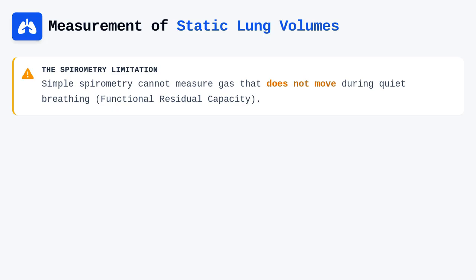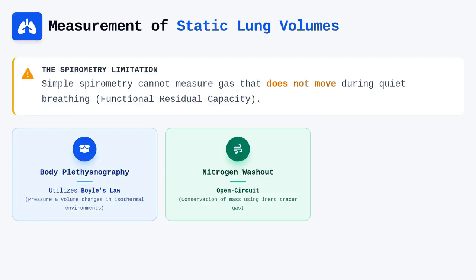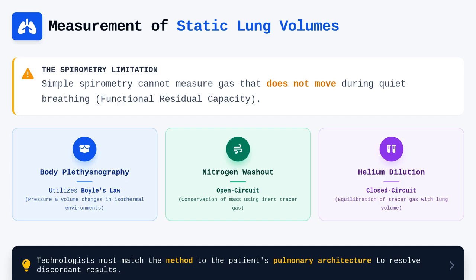When we approach the measurement of static lung volumes, we are essentially trying to quantify the gas remaining in the lungs after a tidal breath, specifically the functional residual capacity. While simple spirometry provides a reliable baseline for flow-based variables, it lacks the ability to measure the volume of gas that does not move during quiet breathing. To capture this, we employ three primary modalities: body plethysmography, open-circuit nitrogen washout, and closed-circuit helium dilution. Each method relies on different physical principles, and understanding their individual operational mechanisms allows a technologist to identify why a patient might show discordant results between tests.